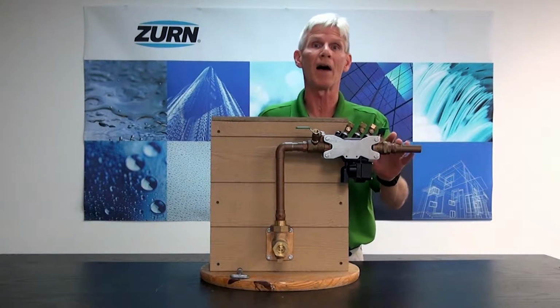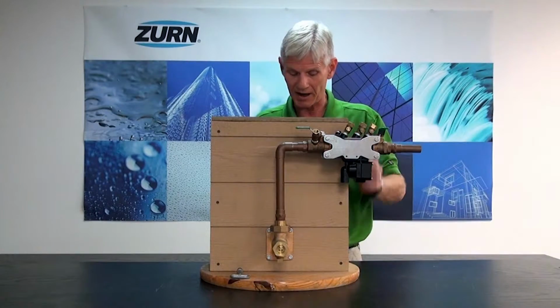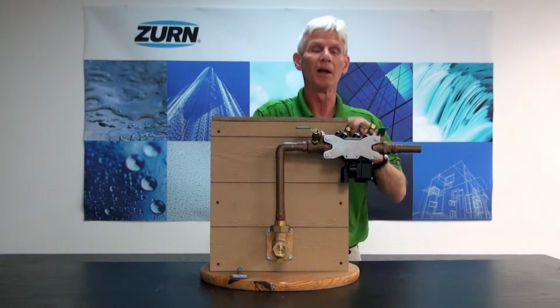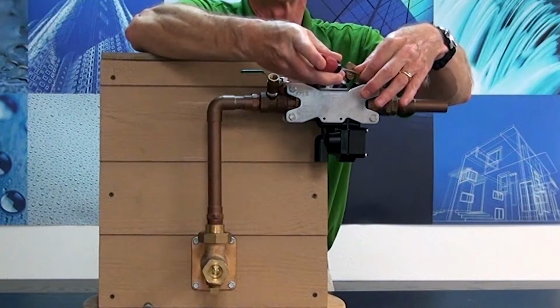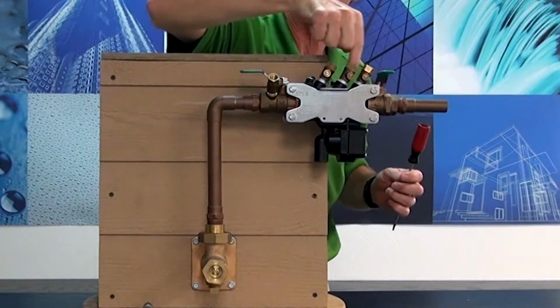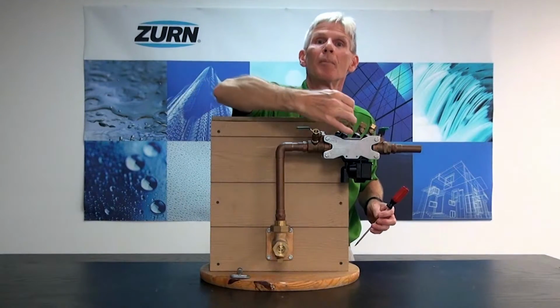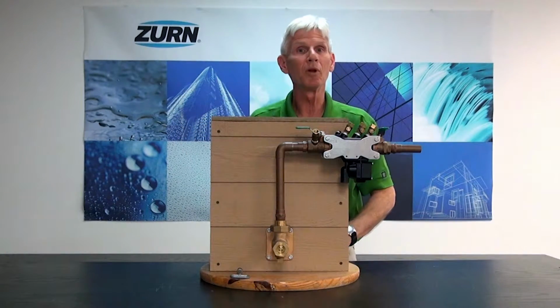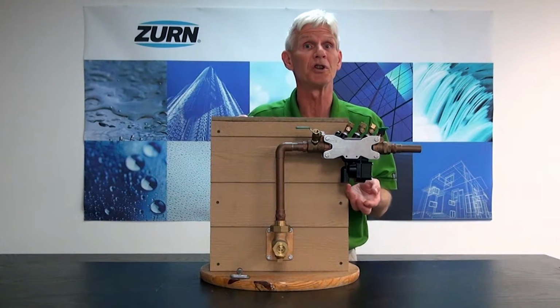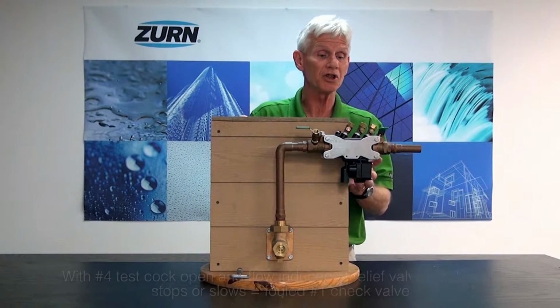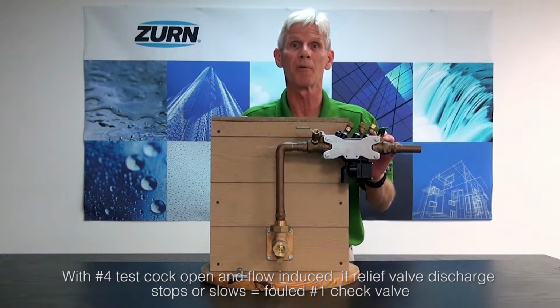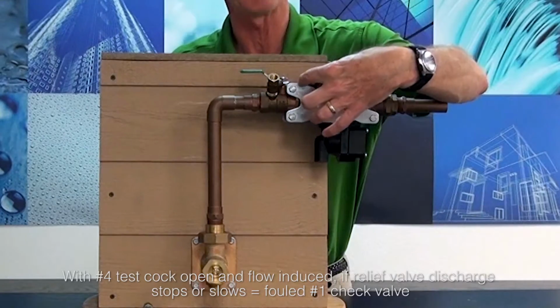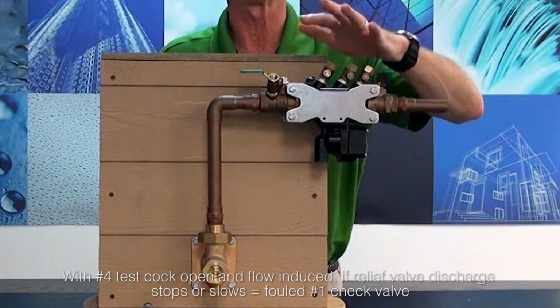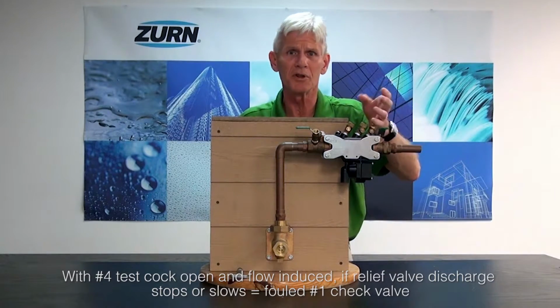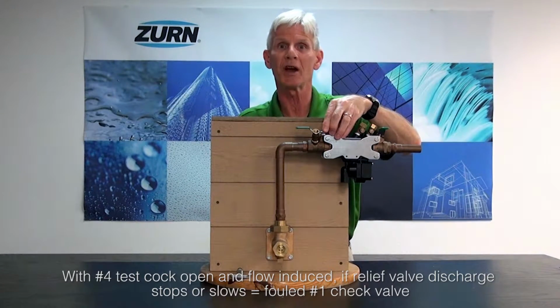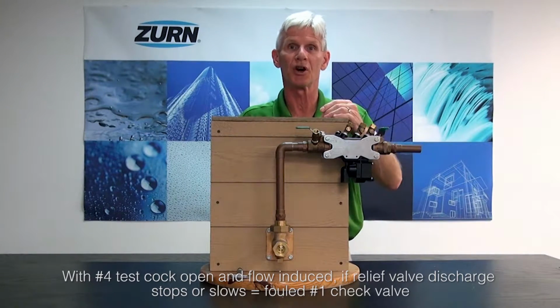Conversely, if I close that shut-off valve and the discharge doesn't stop, what I want to do next is induce a flow through the assembly. I'm going to simply open up test cock number 4. By opening test cock number 4, I now have fluid flowing all the way through the assembly. I develop a good differential across the first check valve. And what I'm looking for now is, does my relief valve discharge diminish or cease? If the relief valve discharge diminishes or ceases while I have test cock number 4 open, that tells me I have a fouled number 1 check valve. So in that case, I'm simply going to shut the valve down, open it up, and again, like we did with the second check, I'm going to repair the check valve so that it no longer leaks, and that will stop that discharge.